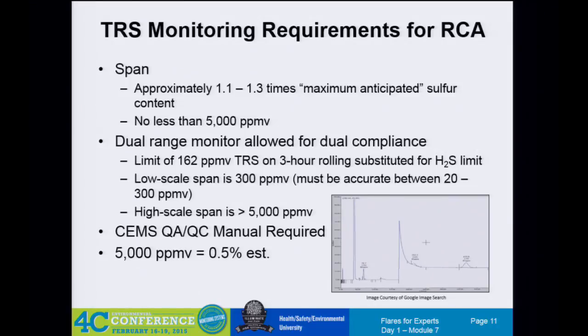You can use a dual range monitor—they did allow that. One of the technologies we talk a lot about for the total reduced sulfur, total sulfur method, is the Thermo Scientific SOLA 2. That's the pyrolysis technique: it burns everything, and the SO2 monitor measures SO2. They said yes, that device does have the ability for two ranges built in, so you could use it for the 162 H2S limit. However, you now have a 162 total sulfur limit, not just H2S. So if you have a lot of these other cats and dogs—other sulfur species in your flare system—you now have an artificially lower H2S limit. So a lot of facilities weren't very comfortable doing that, and most people have gone with a way to directly measure H2S.